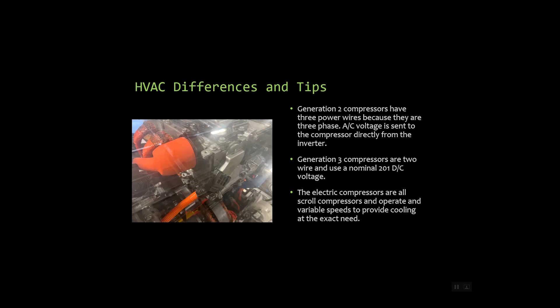The electric compressors are also scroll compressors and operate at variable speeds needed to provide cooling at the exact need. So I can spin this up or I can slow it down depending on evaporator temperature and customer demand, or driver demand, I guess you could say. If the customer's really wanting it cold, I can put that compressor at 100%. But if not, I can slow that compressor down. And of course, this is going to make the system more efficient by using less electricity.